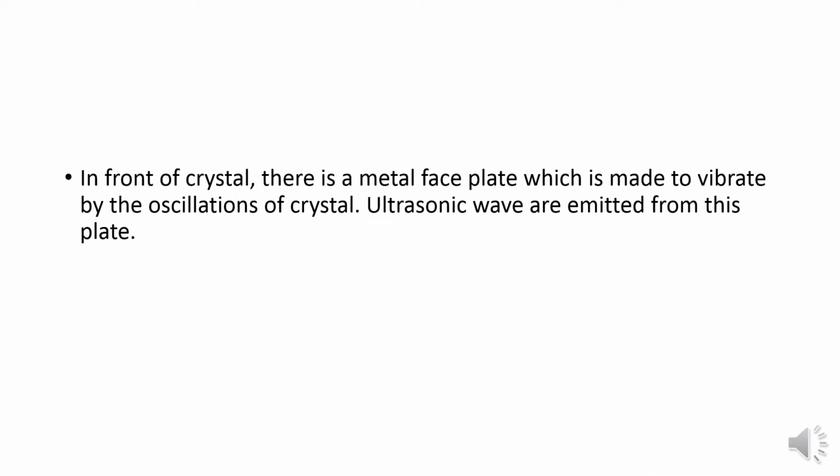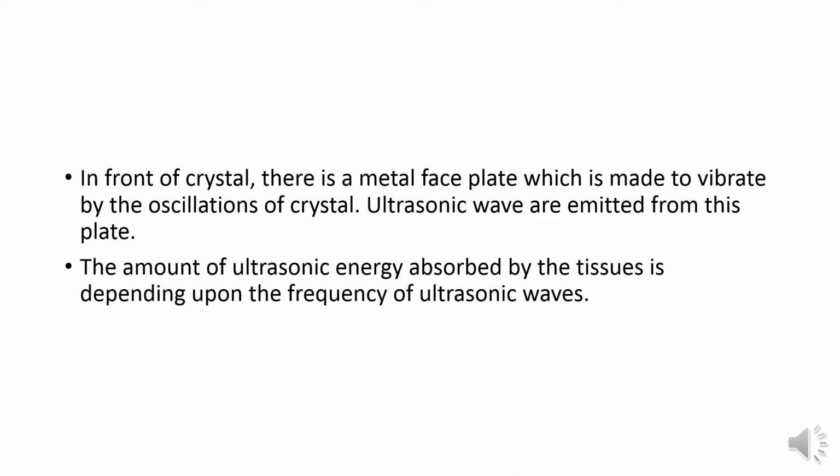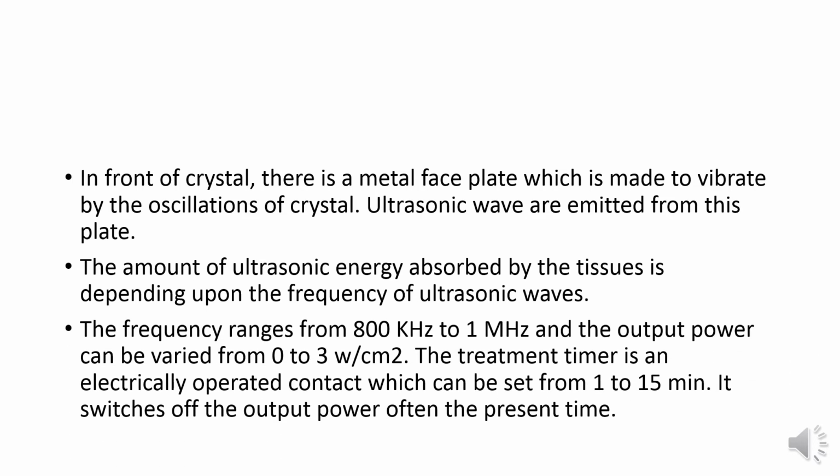In front of the crystal there is a metal face plate which is made to vibrate by the oscillation of the crystal. The ultrasonic waves are emitted from this plate. The amount of ultrasonic energy absorbed by the tissues depends on the frequency of the ultrasonic waves. The frequency ranges from 800 kHz to 1 MHz and the output power can be varied from 0 to 3 watts per centimeter square.